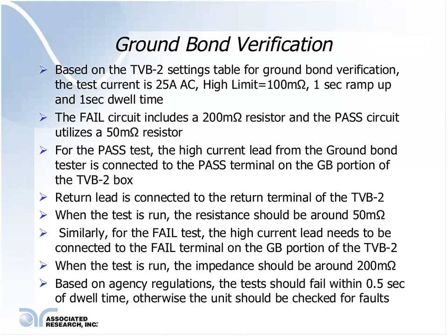So, again, for example, we're going to use the example of the TVB toolbox that we discussed earlier, and we're going to use the same table of resistance values and test settings. And as we know, just like for the voltage withstand test, there's a pass and fail terminal on the box for the ground bond test as well.